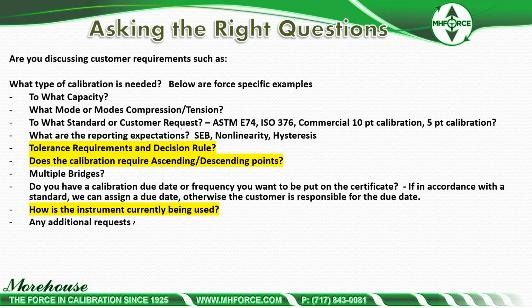If you're accredited, you better be asking this. A lot of people miss this one. Does the calibration require ascending, descending points? How about multiple bridges? Do you have a calibration due date or frequency you want to put on the certificate? If in accordance with a standard, we can assign a due date. Otherwise, customer is responsible for the due date.